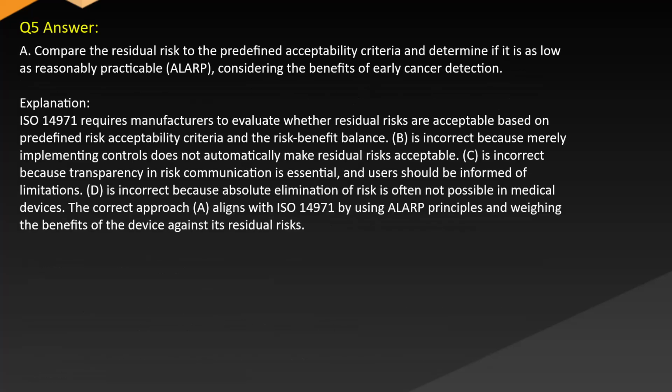Answer A. Compare the residual risk to the predefined acceptability criteria and determine if it is as low as reasonably practicable, considering the benefits of early cancer detection. Explanation. ISO 14971 requires manufacturers to evaluate whether residual risks are acceptable based on predefined risk acceptability criteria and the risk-benefit balance.